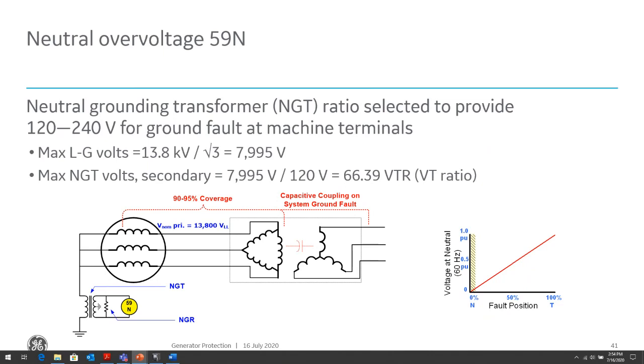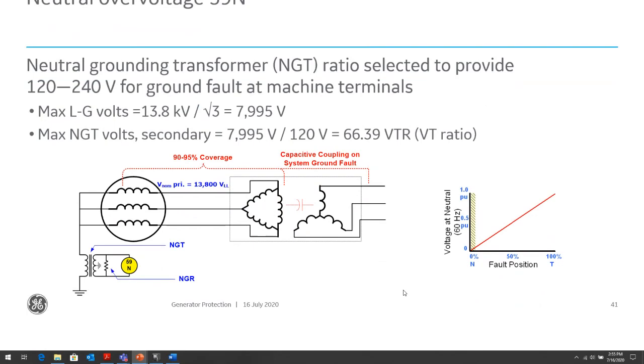So in that case, for low levels of neutral overvoltage, we have a slow-set neutral overvoltage element, which is set to coordinate with our system protection or system ground protection. However, for faults within the generator, the 59N voltage, sorry, not phase to neutral, but zero sequence voltage, will be very high, so we can set that close to instantaneous. So we usually have two stages: an instantaneous stage, which is set pretty high, and a coordinated time-delayed stage, which is set pretty low to coordinate for ground faults in the system.